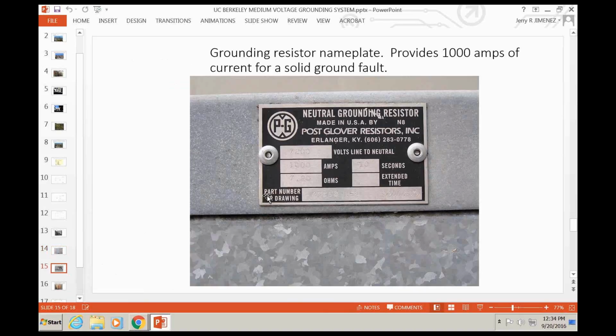So here's a nameplate, just a little more information. 7,200 volts line to neutral, 1,000 amps, 7.2 ohms, with a 10-second rating. We did not pay the extra money to get the extended time, so there is no extended time. You've got 10 seconds, and you'd better clear it by then. Fortunately, most of our ground faults clear well within 1 or 2 seconds. We've never had anything approach 10 seconds.